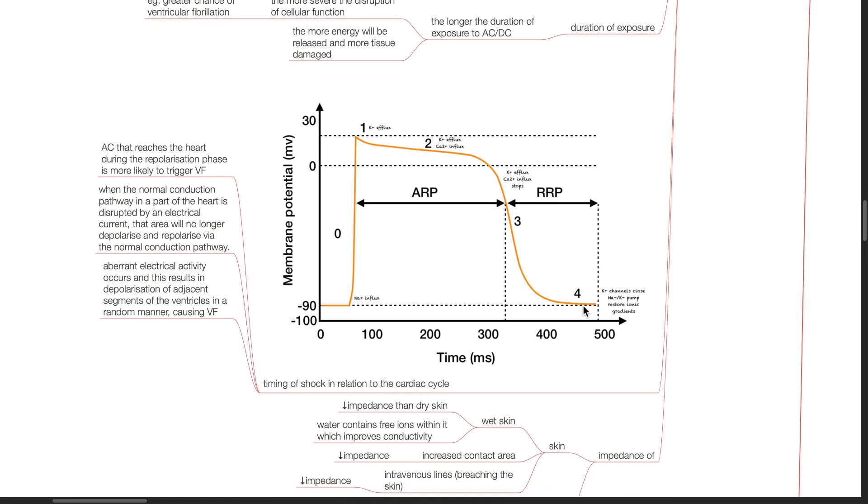Timing of shock in relation to the cardiac cycle. AC that reaches the heart during the repolarization phase is more likely to trigger VF. When the normal conduction pathway in a part of the heart is disrupted by an electrical current, that area will no longer depolarize and repolarize via the normal conduction pathway. Aberrant electrical activity occurs and this results in depolarization of adjacent segments of the ventricles in a random manner causing VF.